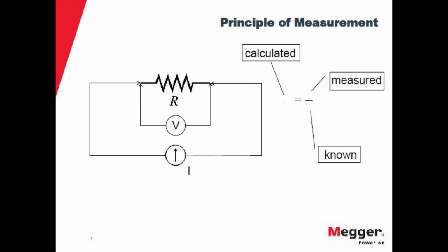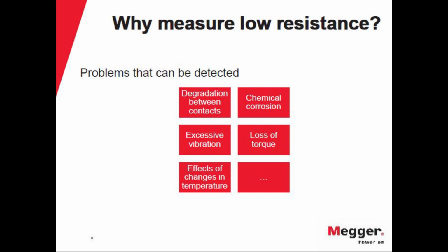You have a resistance, the sample that you want to measure, and you apply a DC current. When current circulates through that sample, you measure the voltage drop exactly between the two points where you want to determine the resistance. With that voltage drop and that current, using Ohm's law, you can determine the resistance of the element you want to test. The voltage drop is measured, the current is known from the instrument, and the instrument calculates the resistance.